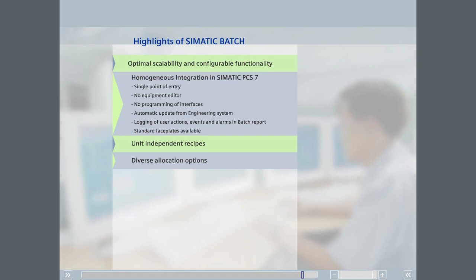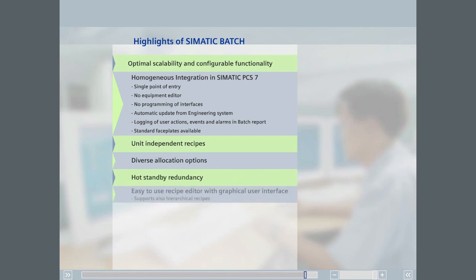An external source such as an MES system can also be used to allocate the unit. To increase availability, hot standby redundancy is available. With the recipe editor, SIMATIC Batch provides a convenient tool that you can work with simply and intuitively to graphically create and administer both flat and hierarchical recipes, with access protection, electronic signatures, and other functions.